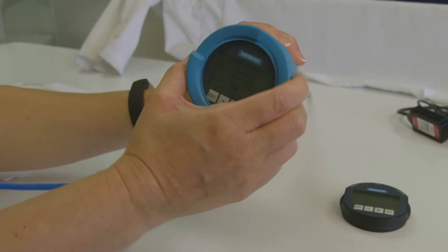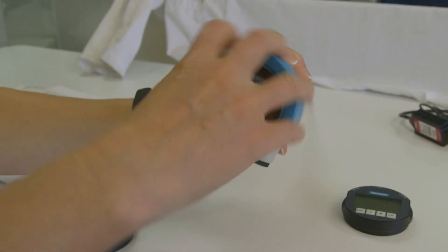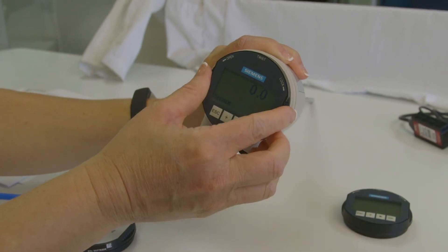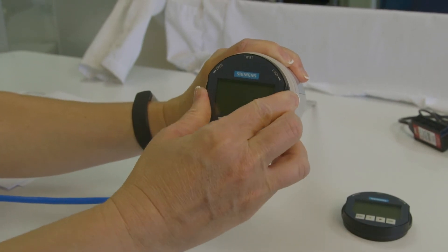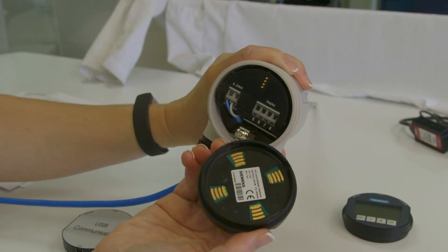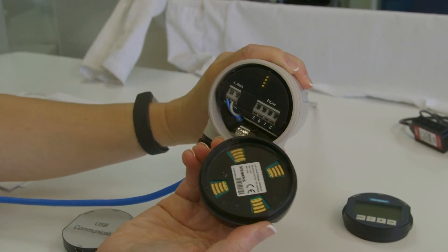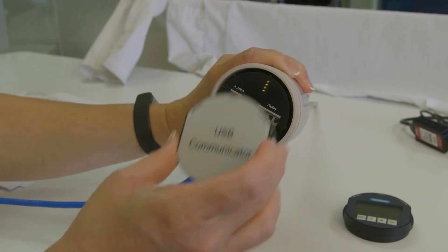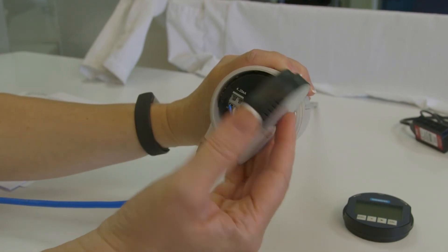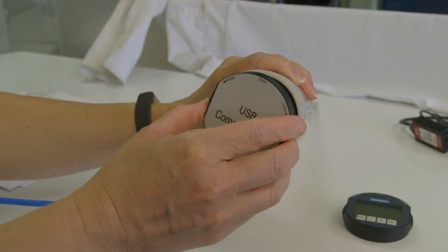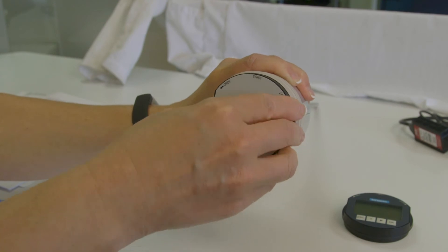Remove the LCD display module and install the USB communicator. Make sure its back connections are in line with the connectors on the module. The back contacts for USB communicator ensures it can only be installed one way. Its USB port will face cable gland side of the housing.